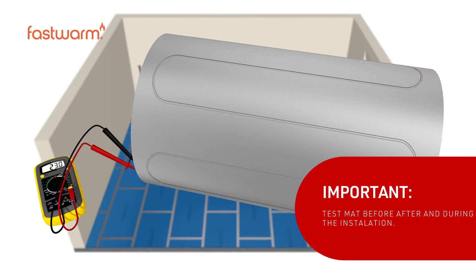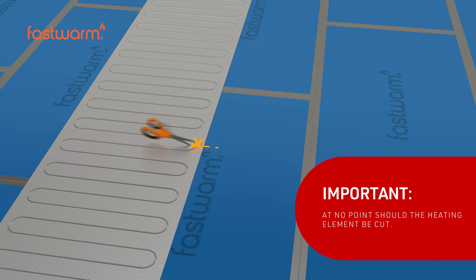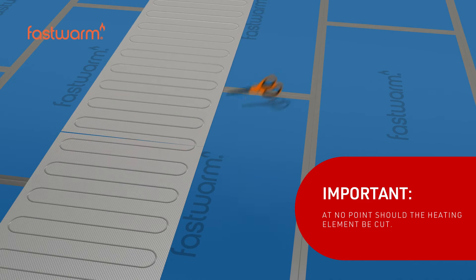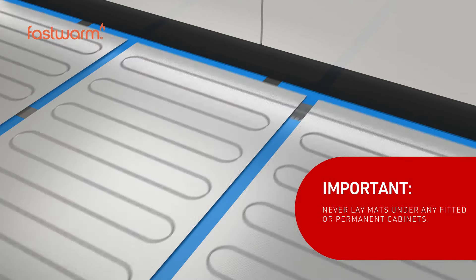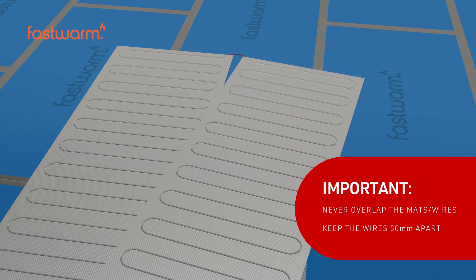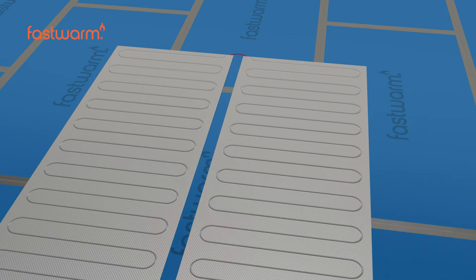The cable within the mat must be tested before, during and after installation. At no point should the heating element be cut. Never lay mats under any fitted or permanent cabinets. Never overlap the mats or cables — ensure the cables are kept at least 50 millimeters apart.